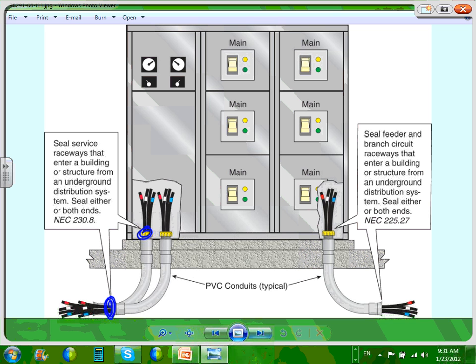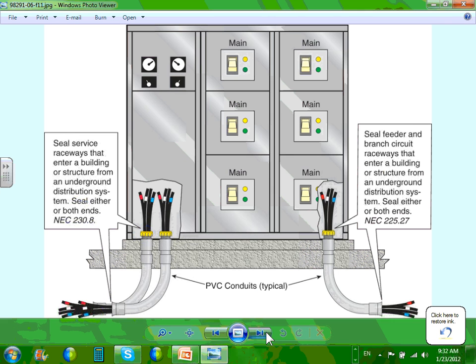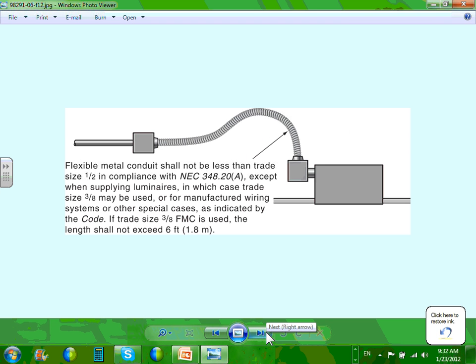By code 2011, you have to seal either or both ends. The reason is they got tired of creatures crawling inside the switchgear and shorting 4,000 amp switchgear and dropping a hospital out of business. So you seal for the most part for animals, and because there's not a whole lot of temperature difference from underground to above ground. But for the most part for creatures. That was changed in 2011, as a matter of fact. Seal from different environments. It has been there for a long time, guys.